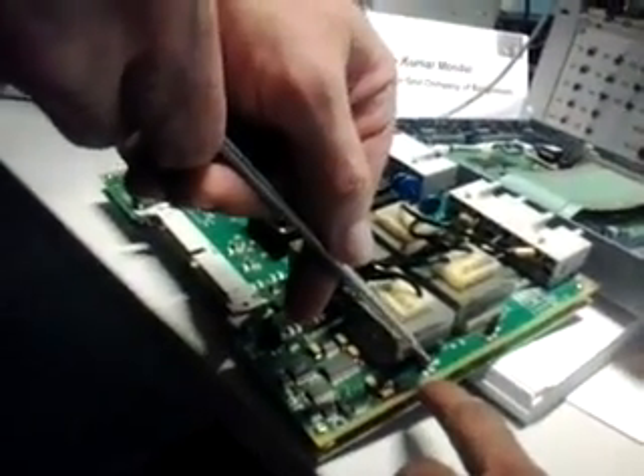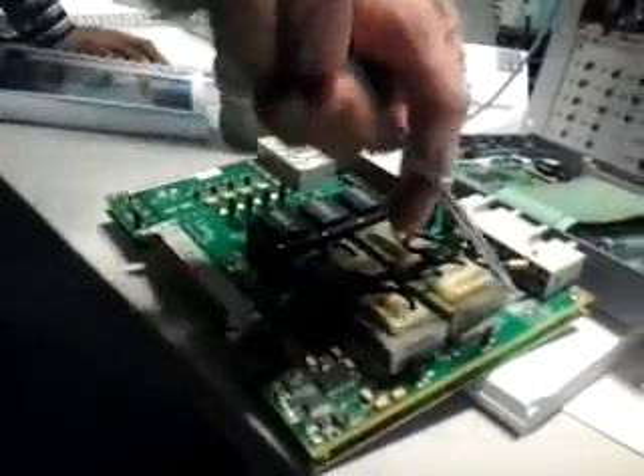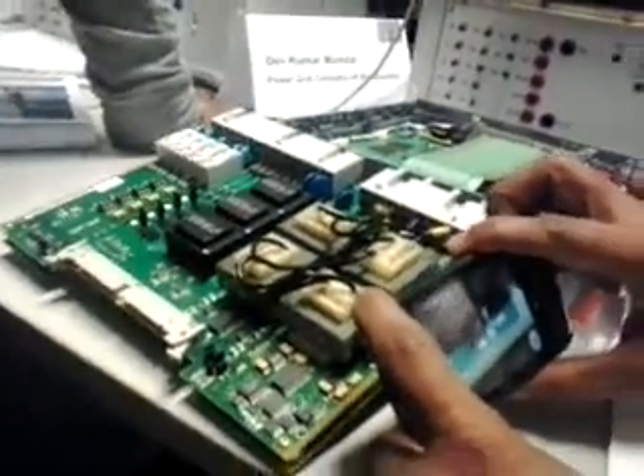Okay, so you see now it's 5A. Because there are three pins — the middle pin is now connected with 5A. Otherwise here, the middle pin is connected to 1A. So this is the situation: 1A or 5A, they have two options. Middle is the common. We should change all four connections, and now comes the very important.